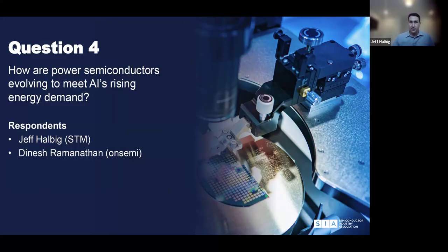Mechanical redesigns are very important. People don't often think about how you package these semiconductors, but it's critically important because you have to get the heat out that they're dissipating. So we see trends in dual side cool packaging, very low profile packaging, to meet power density requirements on the racks. Dual side cool helps get heat out not just from the semiconductor itself but from the total system. For instance, we designed a power delivery board where the semiconductor itself is the cooling conduit from the PC board where the magnetics are embedded—heat from those magnetics goes out through the semiconductor. So these are some of the evolutions.